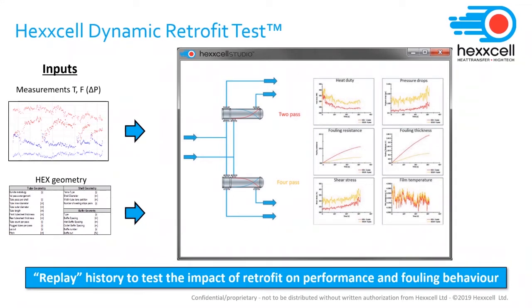Luckily, we have operating data, and together with the information on geometry of the heat exchanger and the dynamic models that allow us to predict fouling, we are able to propose a new heat exchanger design, go back in time, replay history, and assess how the new proposed design would have performed had it been in place in the previous years of operation. We are answering questions like, which is the heat exchanger that would provide the most benefit if retrofitted, or what are the long-term benefit in retrofitting with a more expensive technology in terms of fuel consumption in my specific plant.